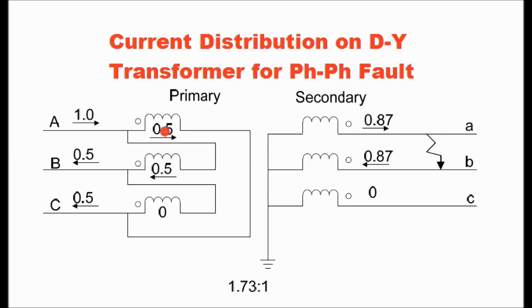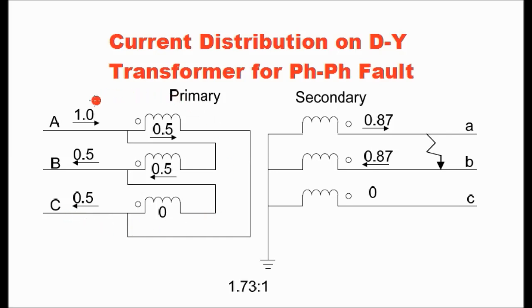Since the red phase and yellow phase currents are exactly opposite in direction, the line current is 0.5∠0° minus 0.5∠180°, which equals 1 ampere for the red phase line. For the yellow phase, only 0.5 ampere flows towards the line, and for the blue phase (C phase) on the delta side, 0.5 ampere flows back out toward the line. This is the current distribution for the delta-star winding for a phase-to-phase fault.